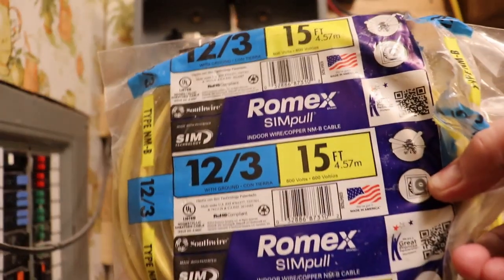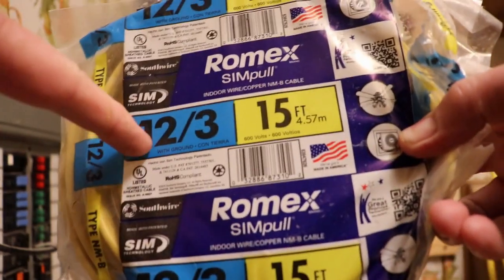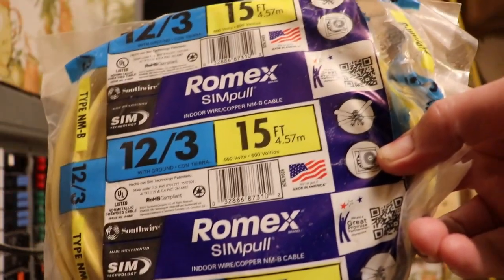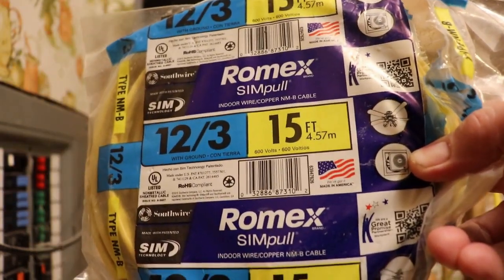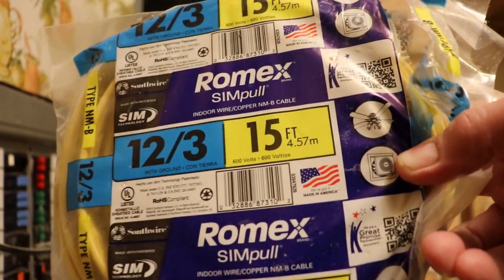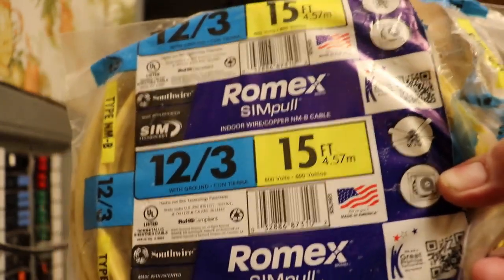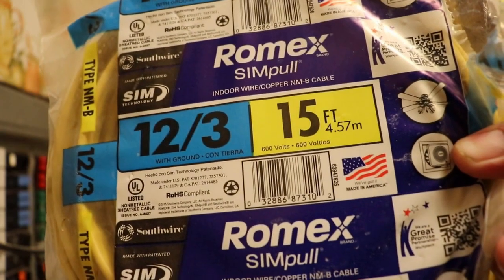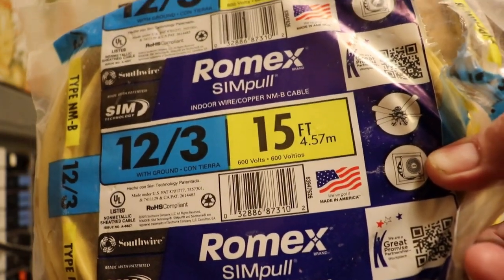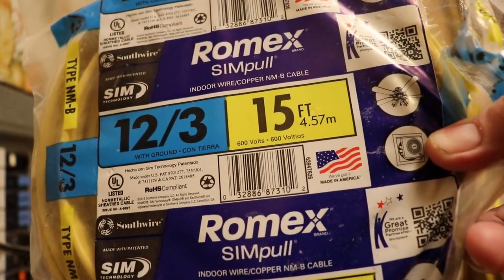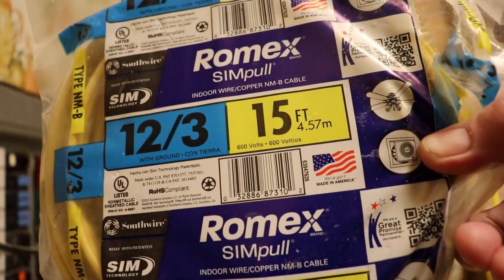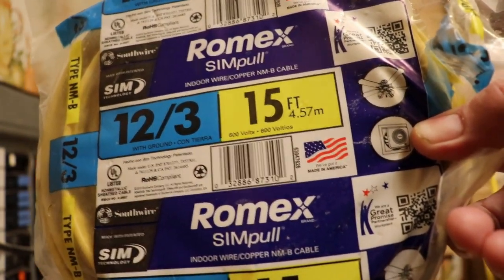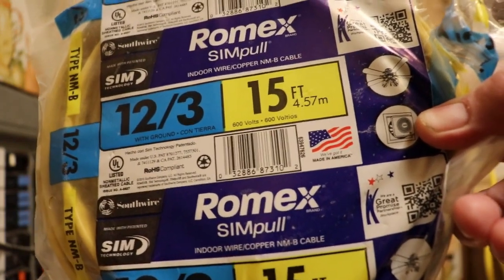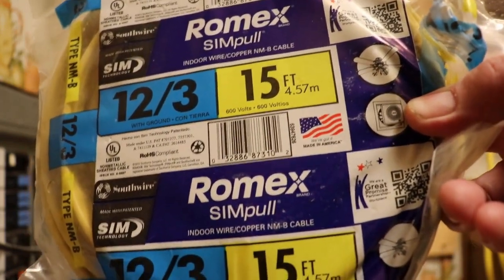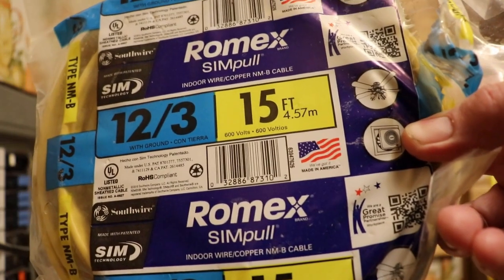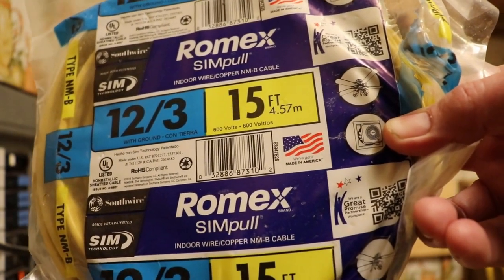Now I'm going to use a 12 gauge 3-wire, about 15 feet of it. The 10 gauge was too much, and since I'm only inputting 15 amps to the inverter anyway—if I plug into a generator, not 30 with the 240 plug, but 120 at 15 amps—this will do just fine. Remember: 12 gauge is for 20 amps, 10 gauge is for 30, 8 gauge is for 40, and 6 gauge is for 55 amps.